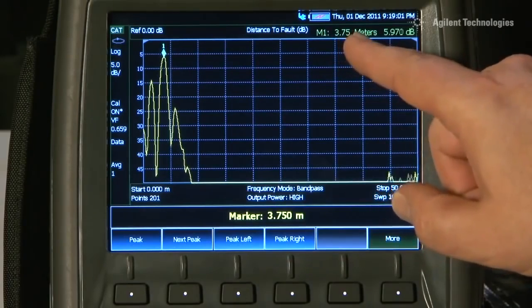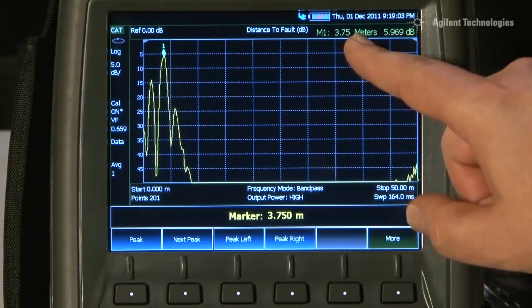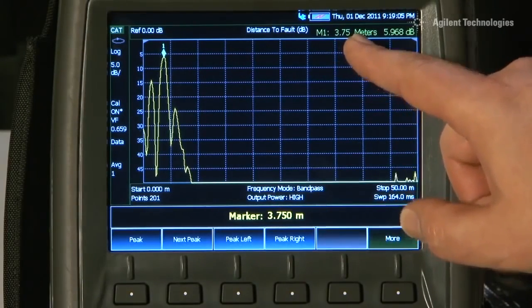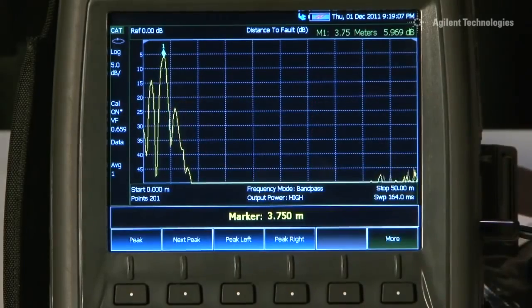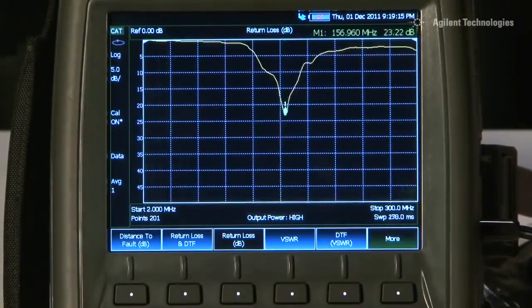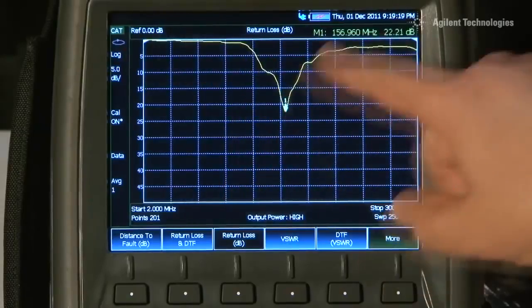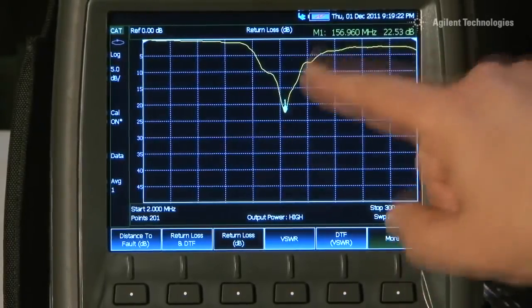that is the join where the cable goes onto the antenna, and the rest is the response of the antenna itself. If I now select the measurement of return loss in dB, we can now see a far clearer display of the antenna return loss.